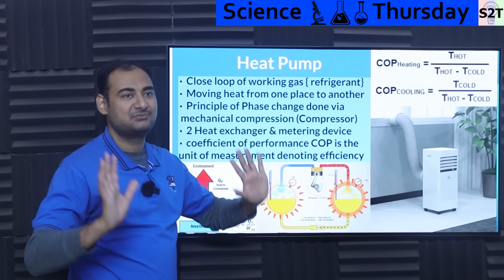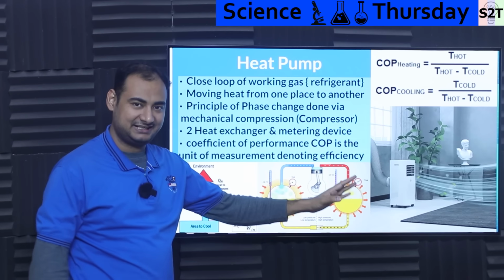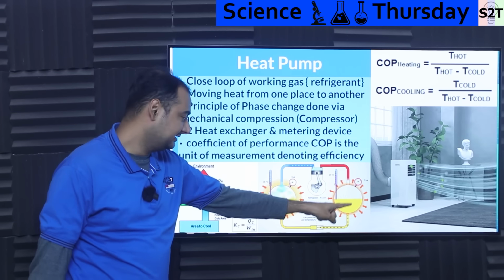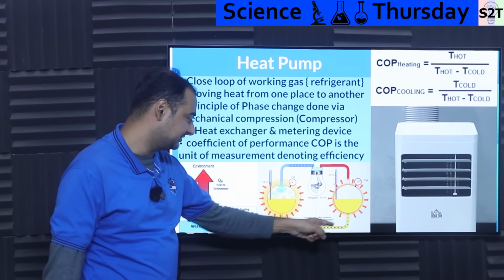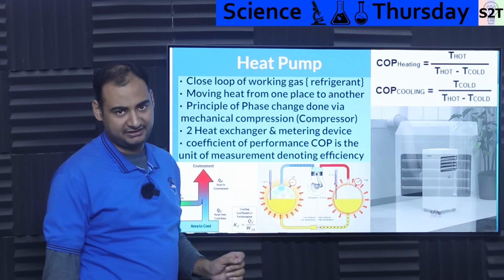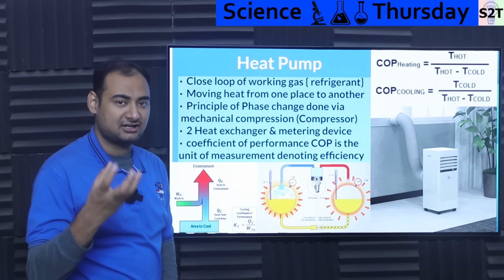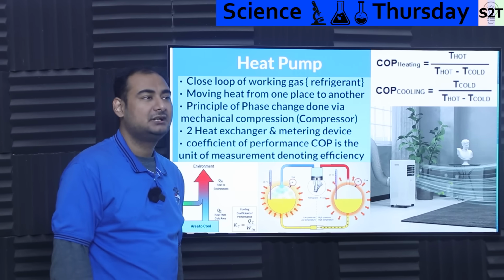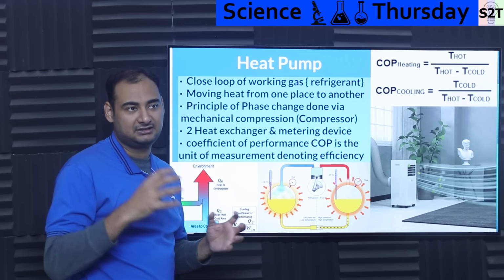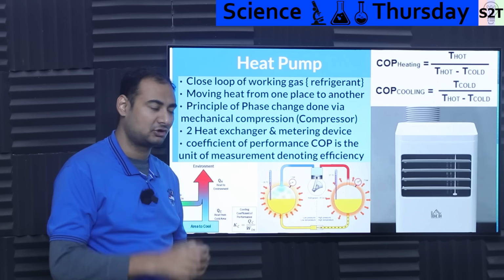At that point, it dumps the heat outside and condenses - now it's a liquid. Because it's a liquid and at high pressure, you send it to what we call a metering device. Now, the metering device is just a valve that allows it to expand in a controlled manner. Modern systems have even controllable valves - basically, it controls the throttle.